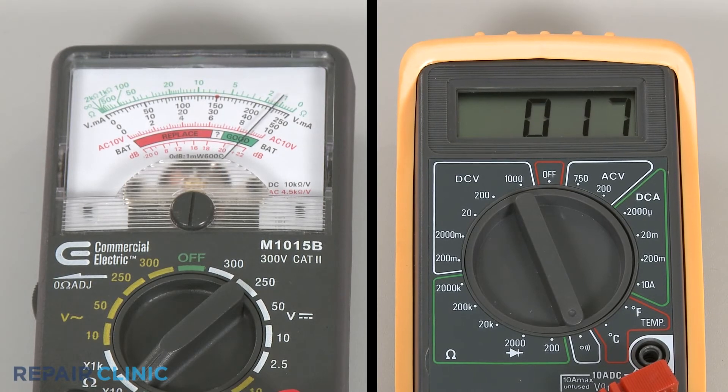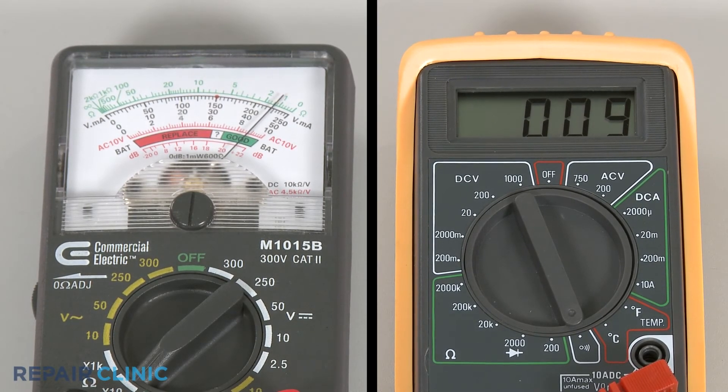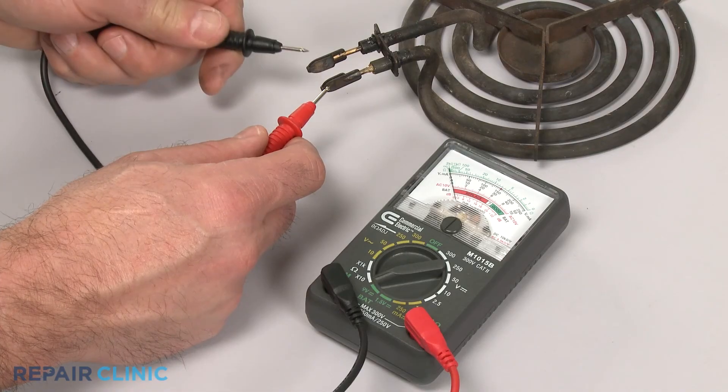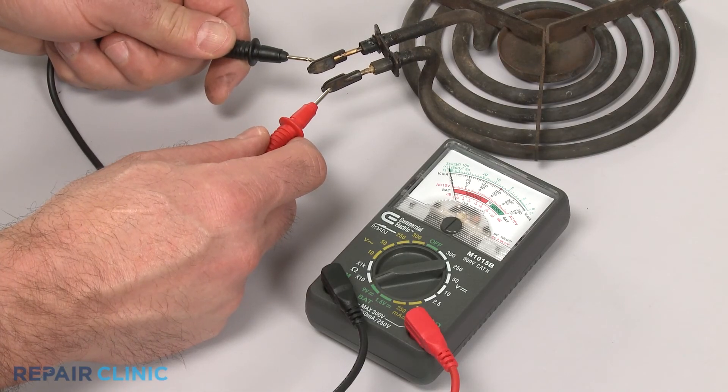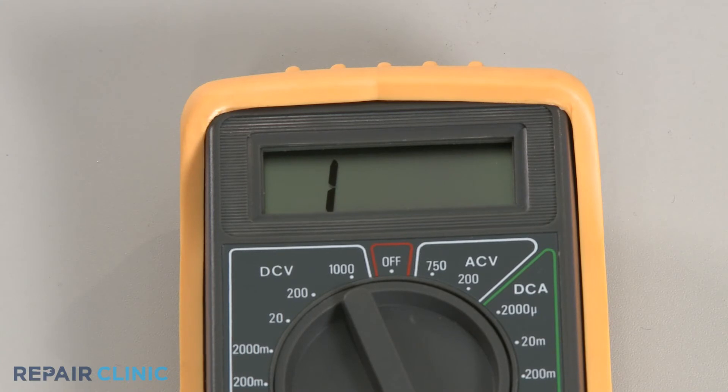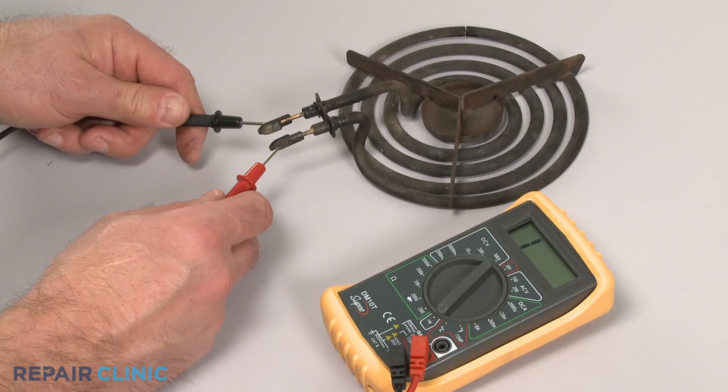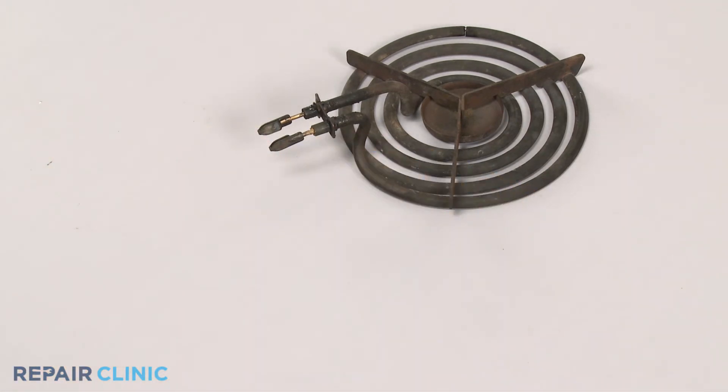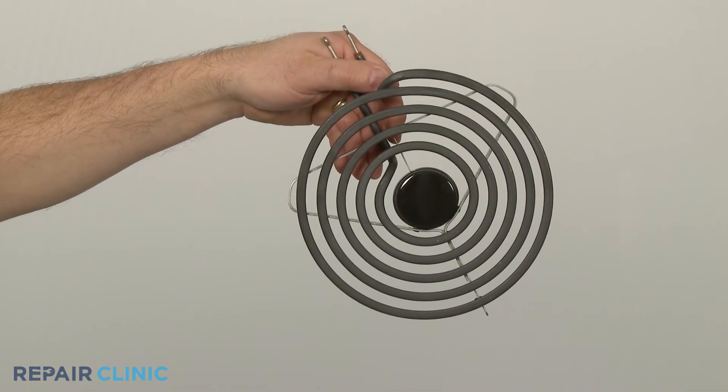If the meter reading shows a result between 0 and 50 ohms of resistance, the element has continuity. If the needle does not move, or the digital display does not change significantly, there is no continuity, which means the element is burned out and will need to be replaced.